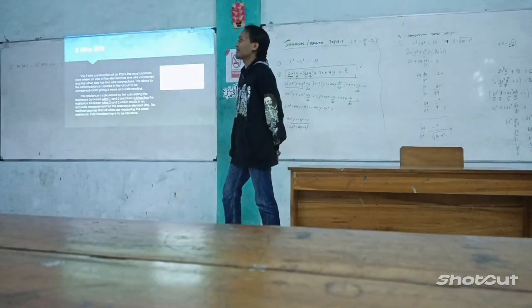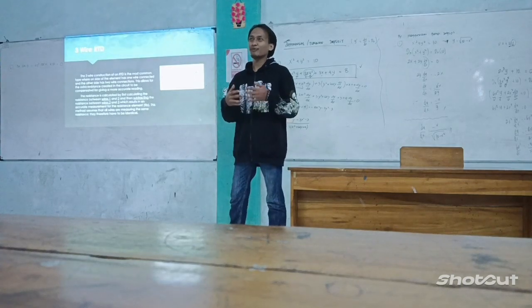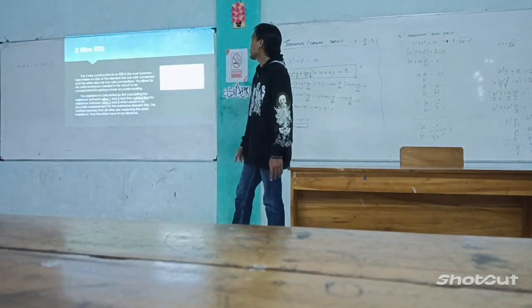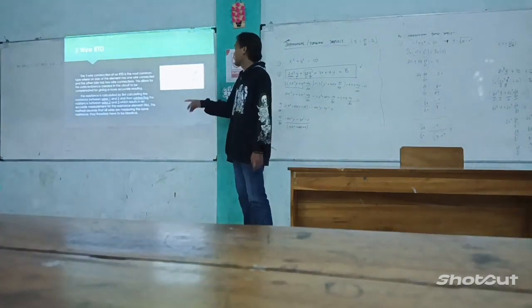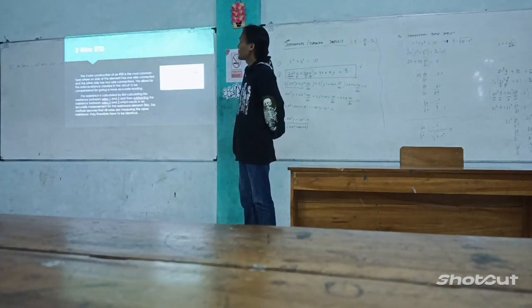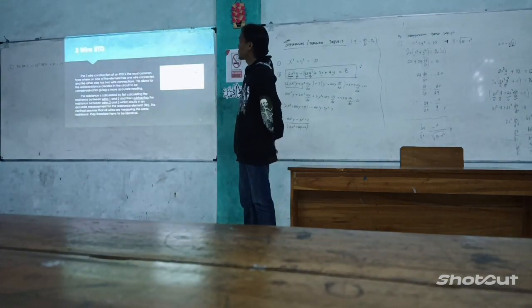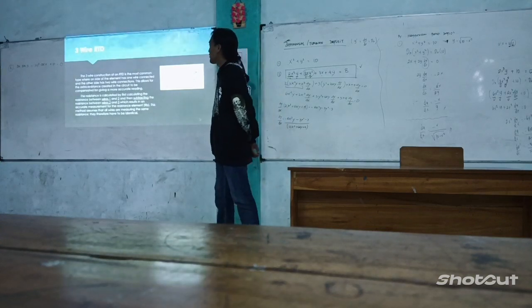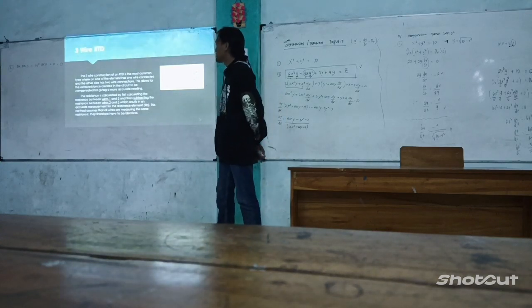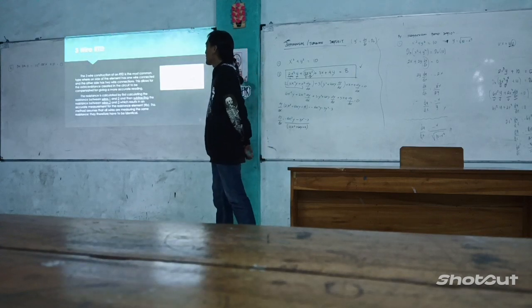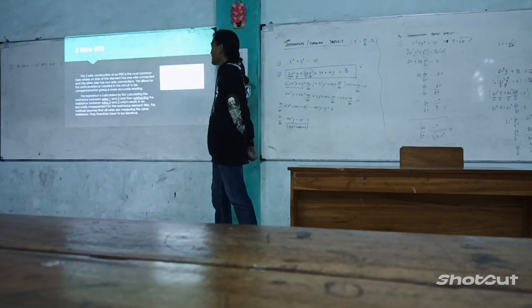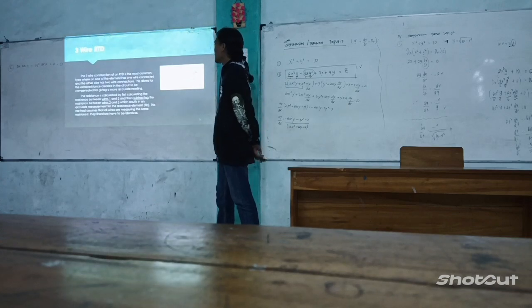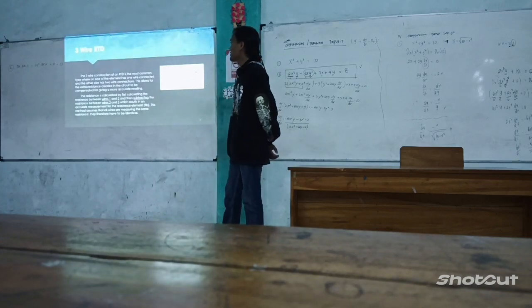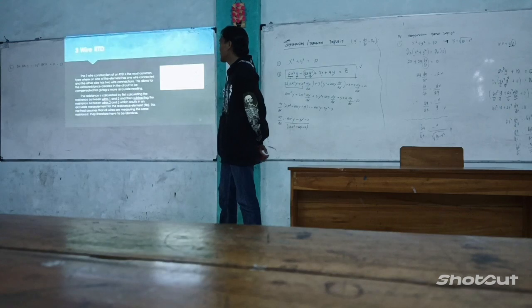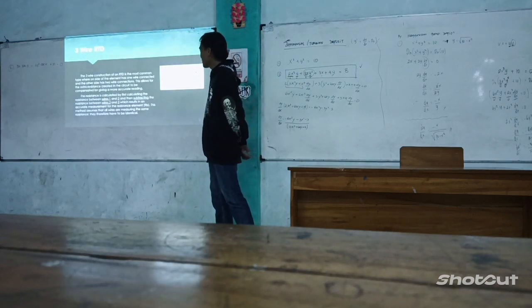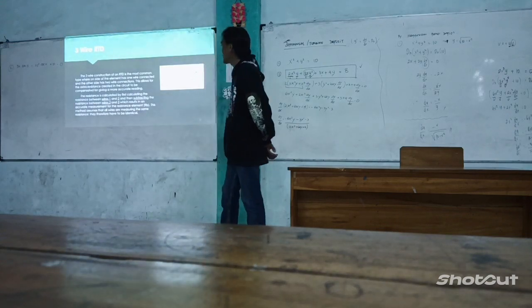In my workplace, the three-wire RTD is the most common, so I will explain how to use the three-wire RTD. The three-wire construction of RTD is the most common type, where one side of the element has one wire connected, and the other side has two wire connections. This allows the extra resistance of the wires in the circuit to be compensated for, giving a more accurate reading.